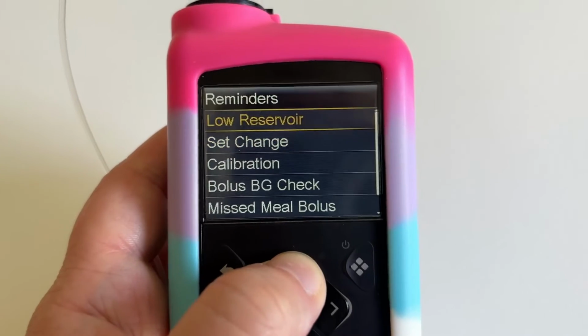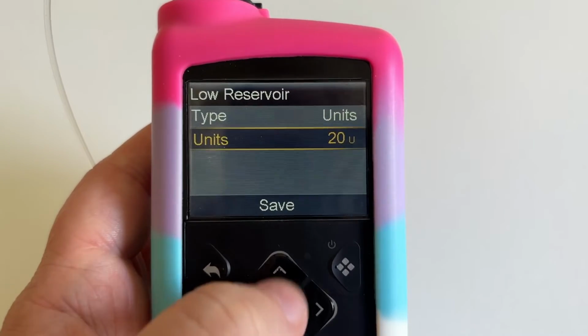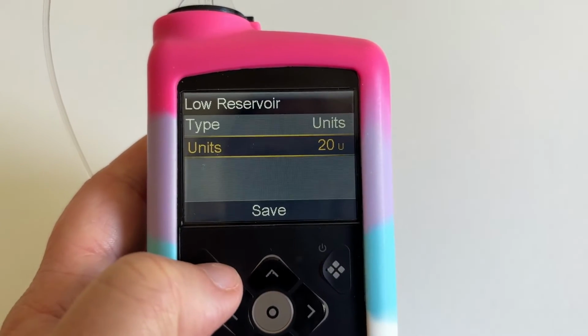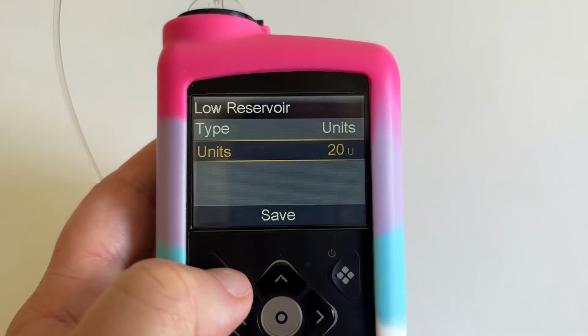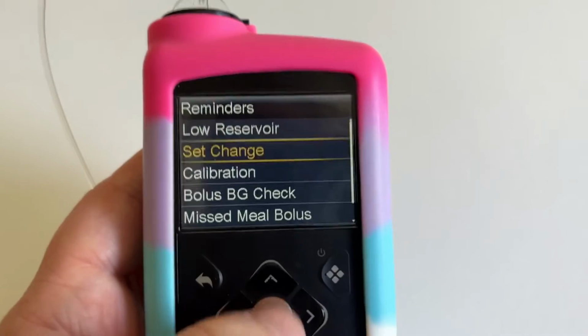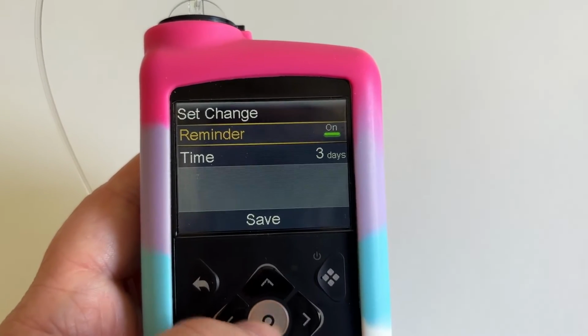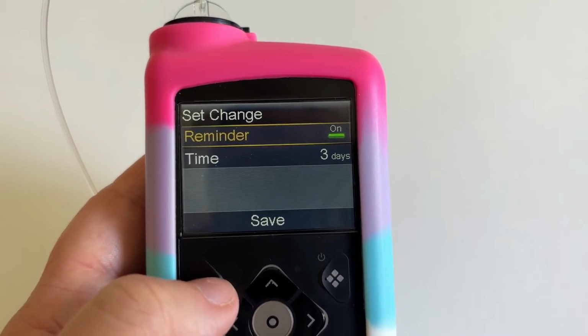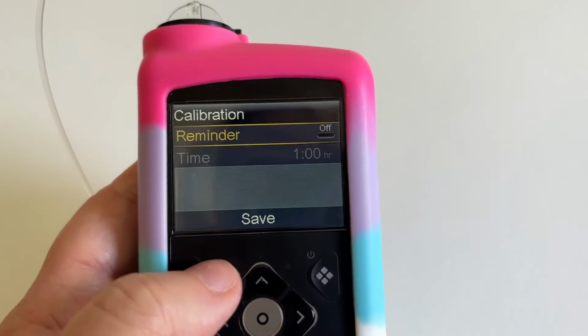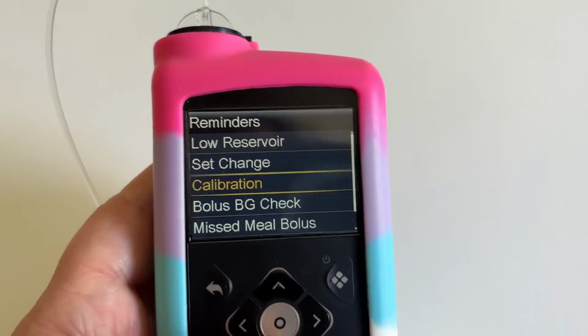So let's have a look in each of them. Low reservoir, mine is set to 20 units. So when my pump reservoir goes to 20 units, it gives me a reminder to change it. Set change, mine is on and it's 3 days. I'll show you how to change this in a minute if you want to make it longer or shorter. Calibration, I don't have this set up. I believe it's just to calibrate the sensor.